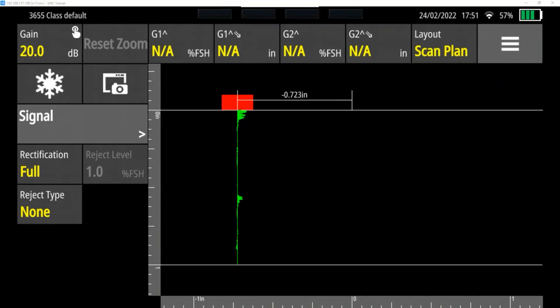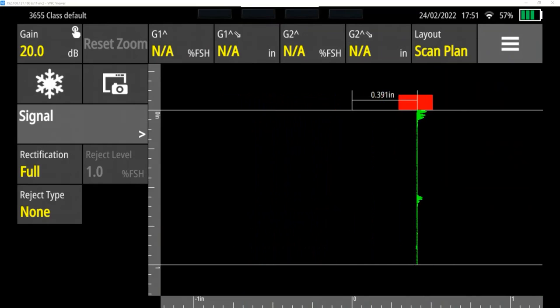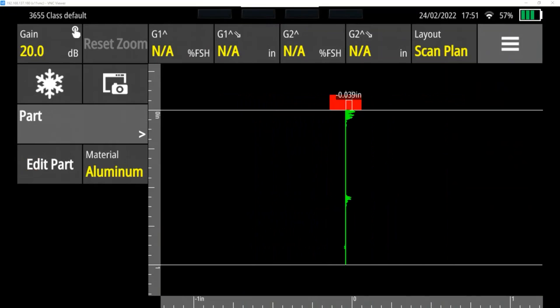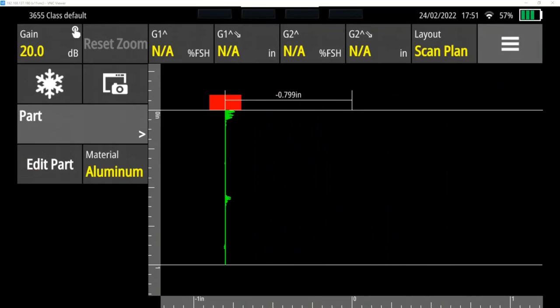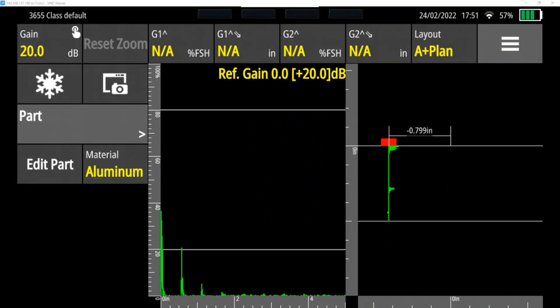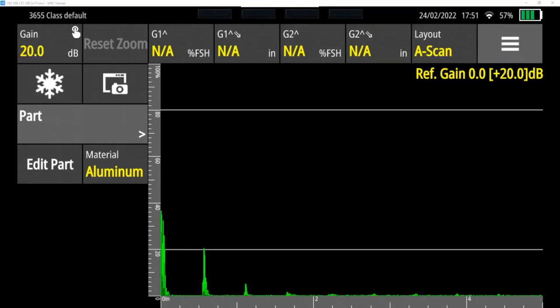And then we also – because we don't use an encoder, we have to manually position our probe in this B scan. And then you can also show the A scan plus the plan scan or the simulated B scan side by side. We're going to stick with A scan.